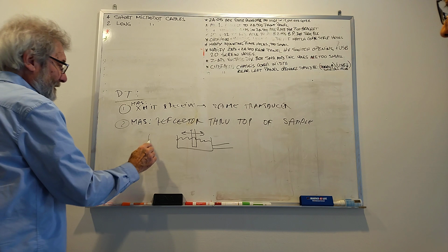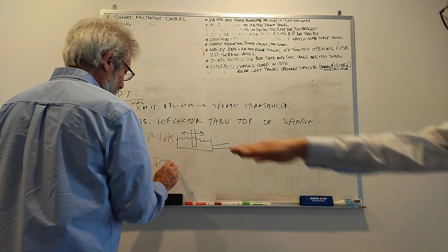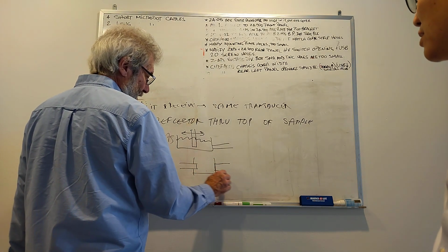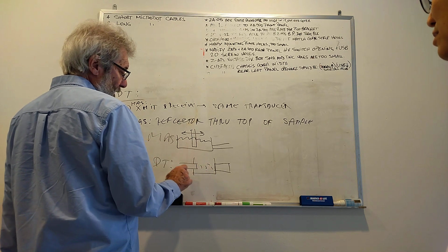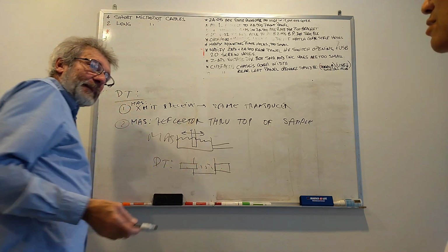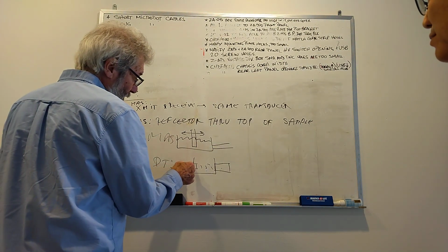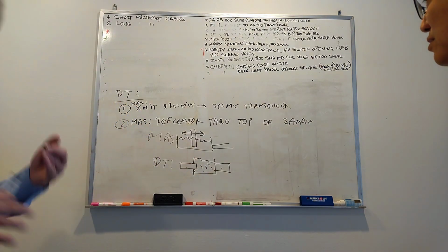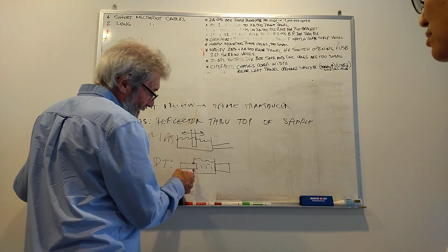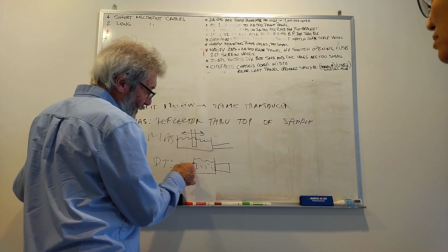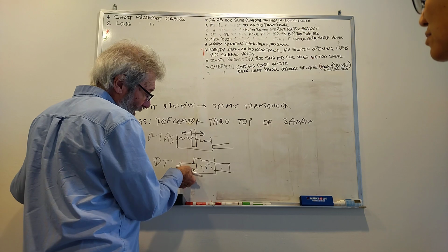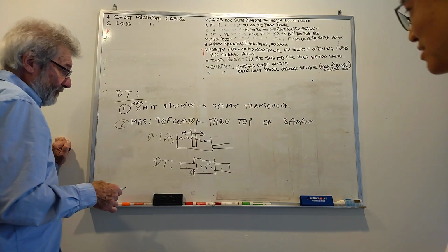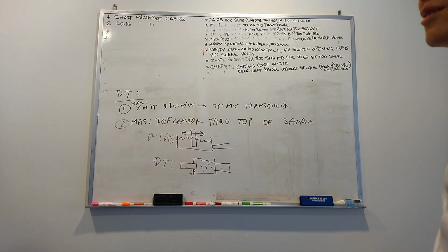So this is mass, but DT goes through the wall. So it needs to have an opening here and another opening here, and through transmission. So you have a problem with two different transducers making measurement, but also you need an O-ring here, and these are always samples. Samples are abrasive with particles, and so this O-ring ends up failing. So you have leaks. It has to be replaced. You lose alignment when it's working, and you have to realign when you replace the transducer. So those are two big advantages.